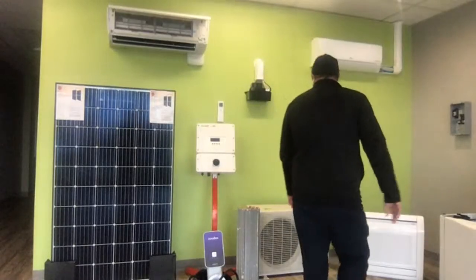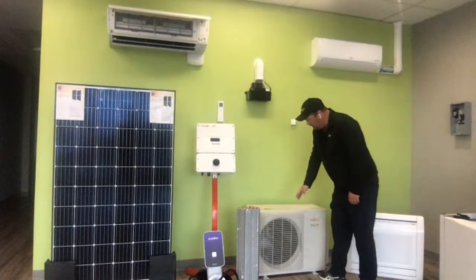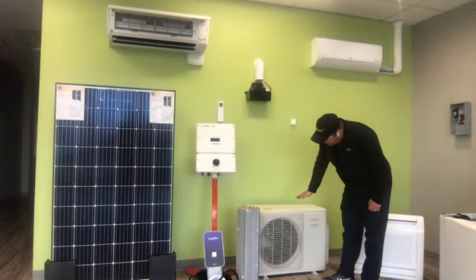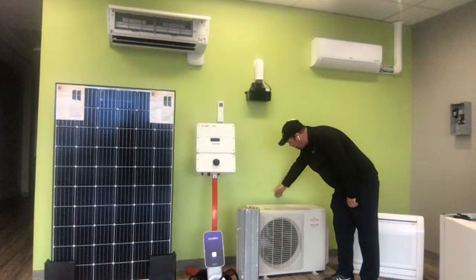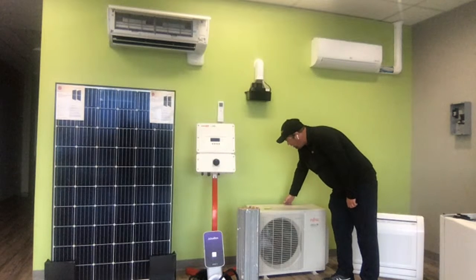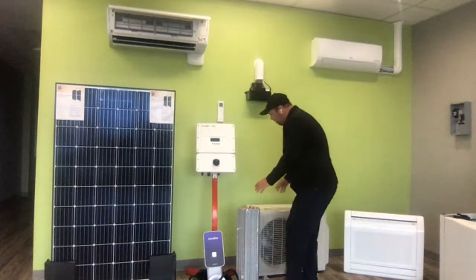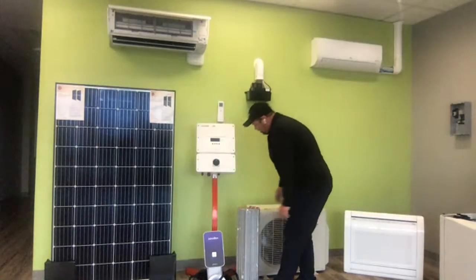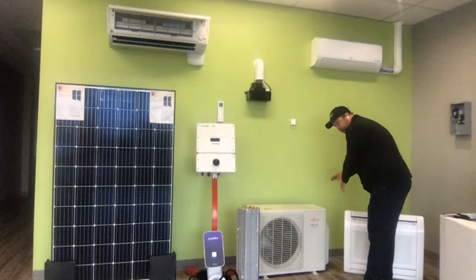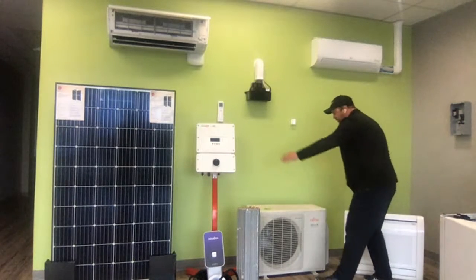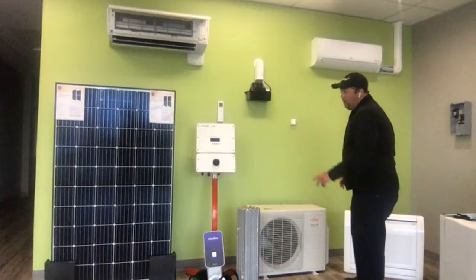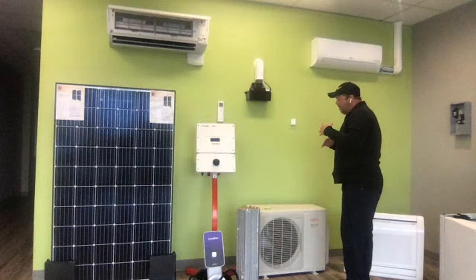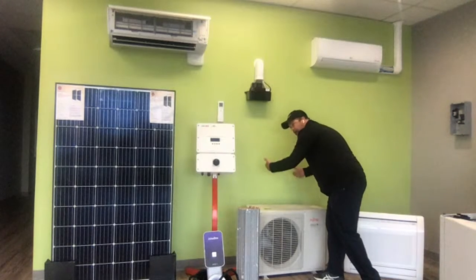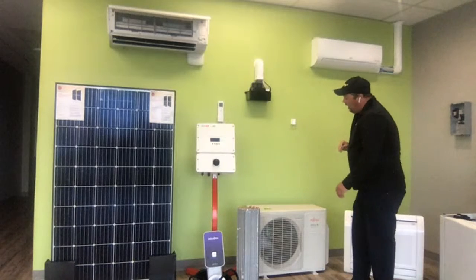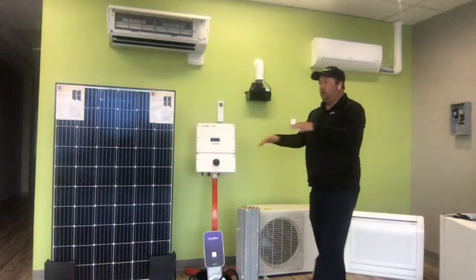How much space do you need for the outdoor unit? I think the outdoor unit is about 28 inches wide, and about 26 high. It has to be out from the wall by a little bit, like 10 inches or something. So you don't want anything directly on the side, though you can have a foot or two either side. You can't put anything in front. It can go below a deck in a lot of cases, but we still need enough room to get the lid off to service it. You can't lattice in a deck, you can't enclose it.